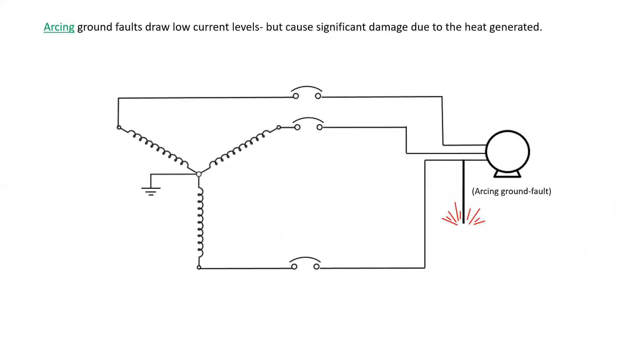Arcing ground faults draw low current levels, but cause significant damage due to the heat generated. If only 2 amps is flowing, there's no way that the breaker will trip because it has not met the minimum threshold for the breaker rating.